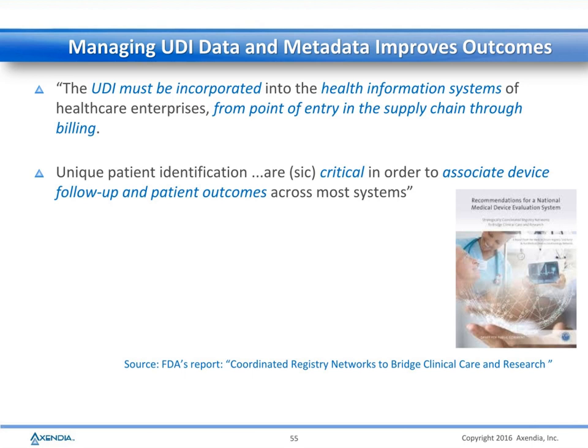Yes. MedSun, for those of you who may not have heard that term, is the Medical Product Safety Network. It is a partnership between FDA and hospitals for reporting adverse events. Those adverse events are reported on a website that FDA puts together through that program. That website now includes a way to enter UDI data, and once the user enters the UDI, the website will split it up into the device identifier and production identifier, and auto-populate the fields that are relevant in adverse event reporting. By having that available, the device identifier can be linked to a patient's record as that becomes available, and to a registry as that becomes available.